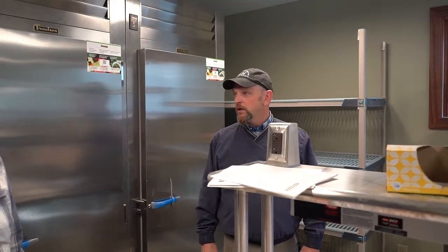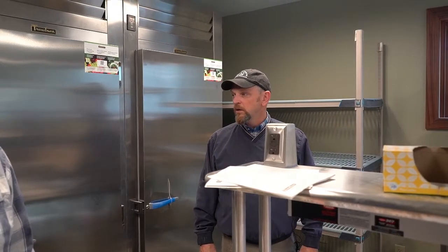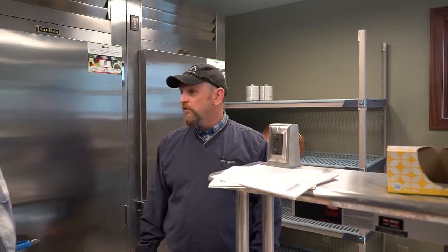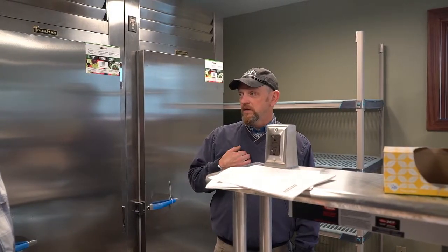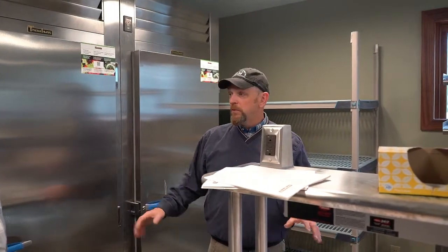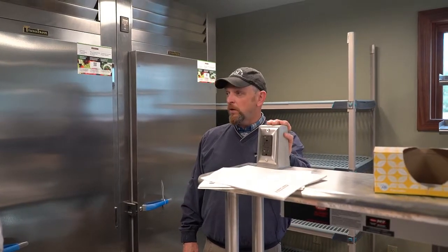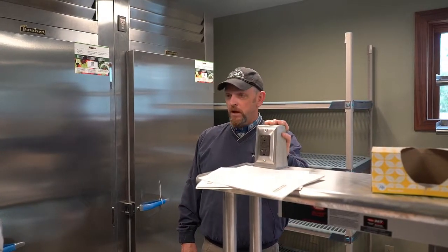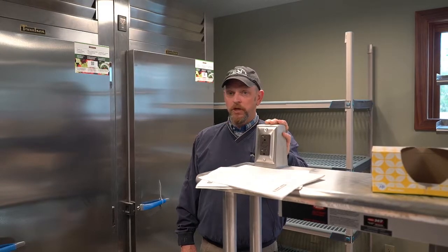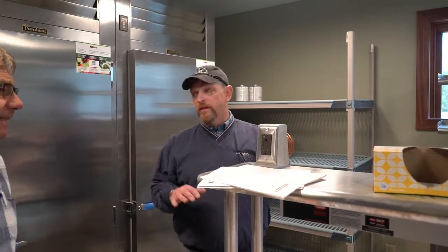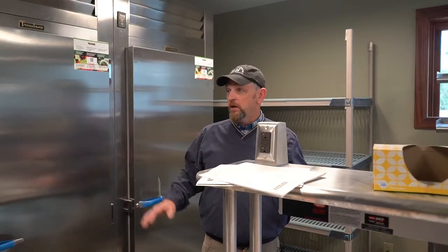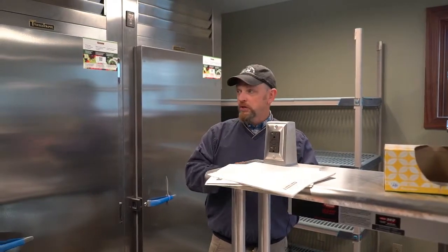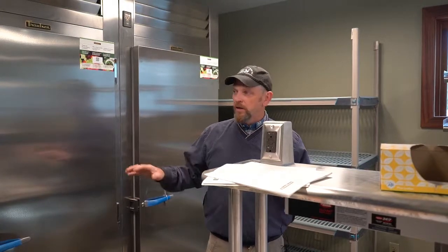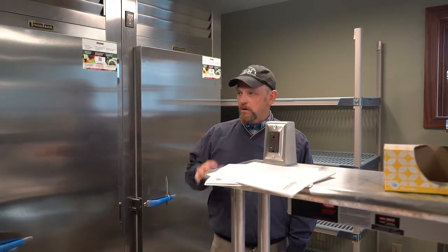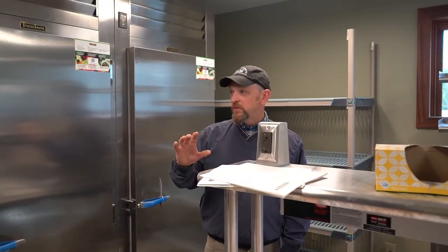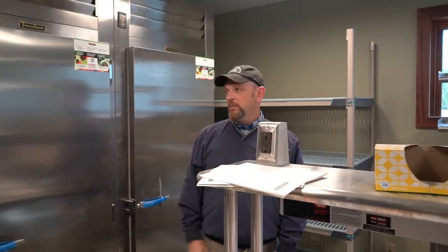The GFCIs that you put in, are they self-testing ones? Honestly, we haven't put any GFCIs in. The only GFCIs in the lobby area are the ones that came pre-installed on the equipment. So the breakers are the GFCI protection. Everywhere that's required to have GFCI protection, next to sinks, anywhere that could get water, outside, even though you don't see the GFCI right there, it's protected back at the panel.